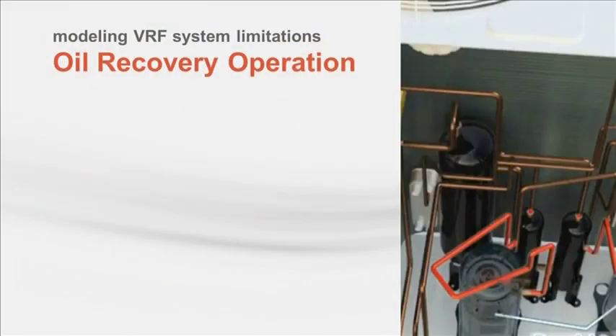Remember the oil recovery or flush cycle that Paul talked about earlier? Any oil that has made it past the oil separator must be periodically recovered. During the oil recovery operation, the system's ability to provide conditioned air is limited, which will affect the space, temperature, and load. This is something that is difficult for simulation programs to estimate because the operations are unique to system manufacturers and oil recovery cycle durations vary.